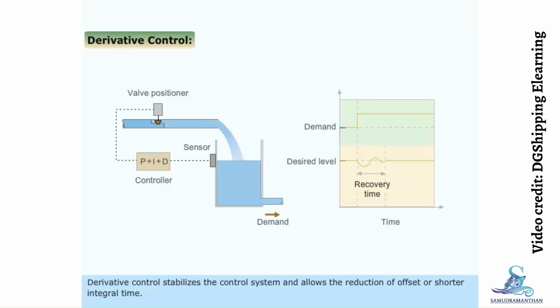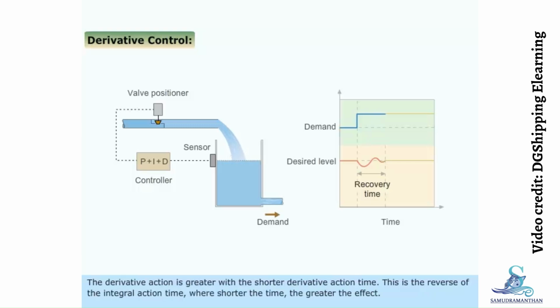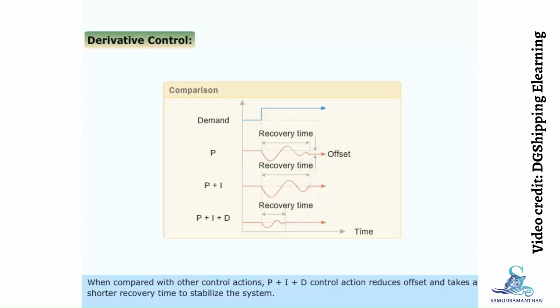Derivative control stabilizes the control system and allows the reduction of offset or shorter integral time. The controller output signal is proportional to the rate at which the error is changing and not upon the value of error. The derivative action is greater with the shorter derivative action time. This is the reverse of the integral action time, where the shorter the time, the greater the effect. When compared with the other control actions, P plus I plus D control action reduces offset and takes a shorter recovery time to stabilize the system.